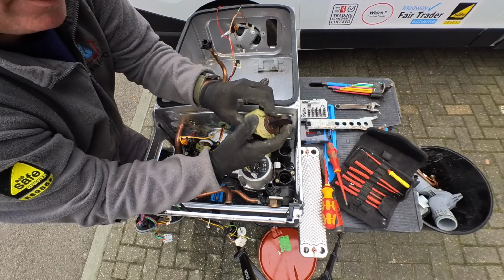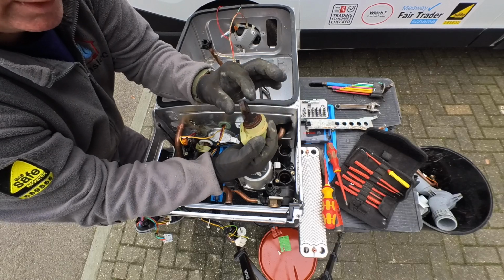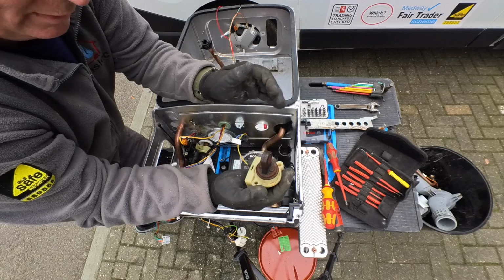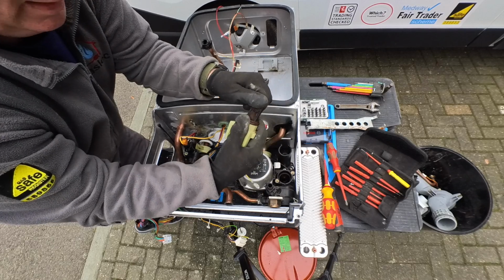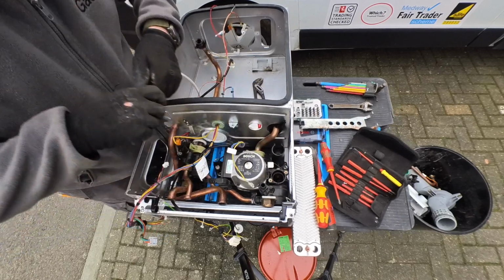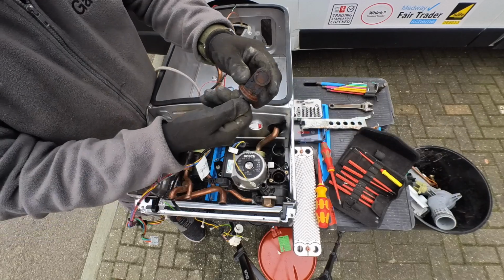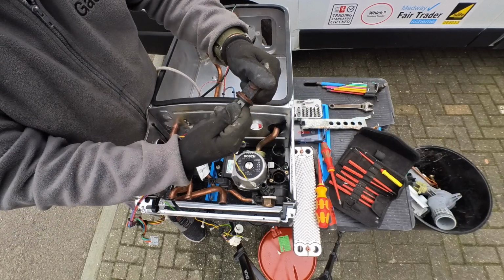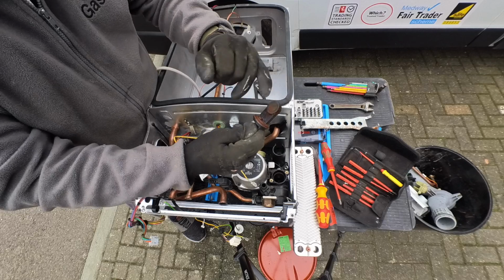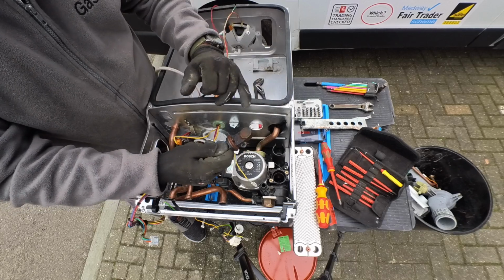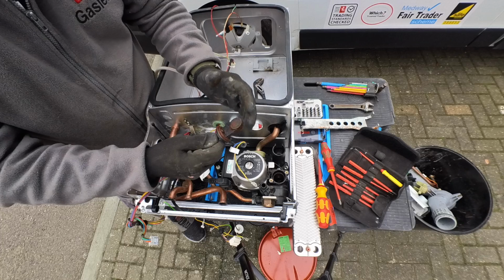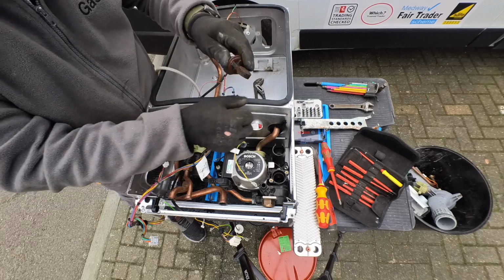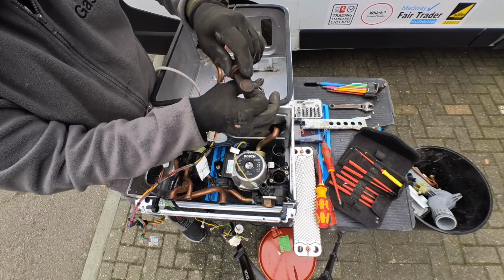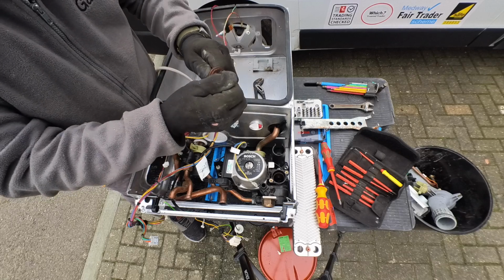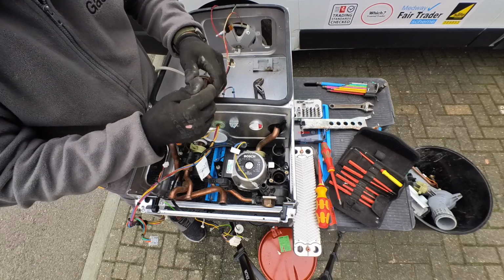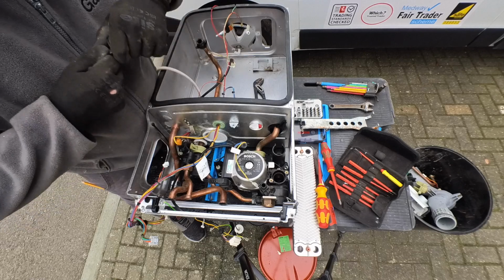As we can see here, this little paddle, they're not quite square, and they block off the two waterways. These things go hard. Pull it out - they go hard, then get all the rubbish on it, and then we start getting the creep. So when you have your hot water on, you start getting a bit of creep through your radiators, because it's not sealing off the pipe properly as it comes across.